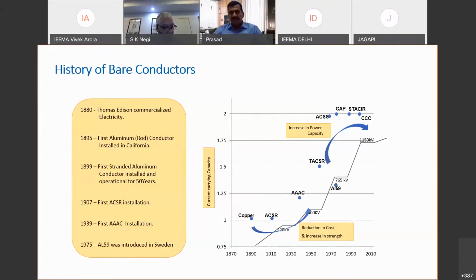Days came where we could feel the requirement of a reinforcement material, because the first stranded conductor was the AAC conductor. It had all aluminum EC grade wires. So the steel core was put inside, and we got the first installation of ACSR conductor in 1907. ACSR conductors had their own merits over AAC conductors.